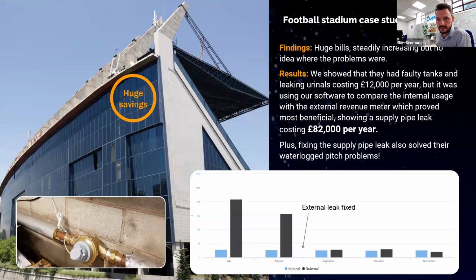So, case studies - this is a really good one. It was a football stadium, but it really could have happened anywhere. They had an external leak that had been going on since records began, and the way we found it was essentially our system was plumbed in on the inside, and they were putting in their water meter data every month. All we did was compare it inside the software, comparing inside with outside, and there was a huge gap, as you can see in July and August, comparing the blue and the black. You don't have to be an expert to see there's a significant amount of waste, and this is done in pounds - almost seven grand a month.